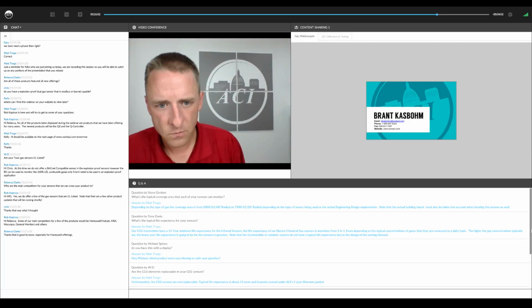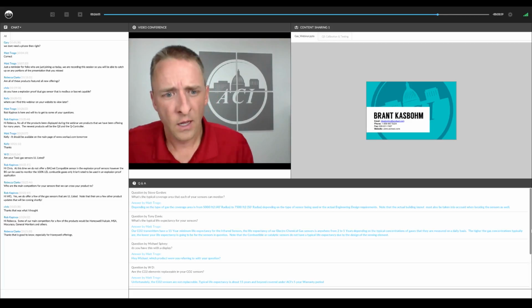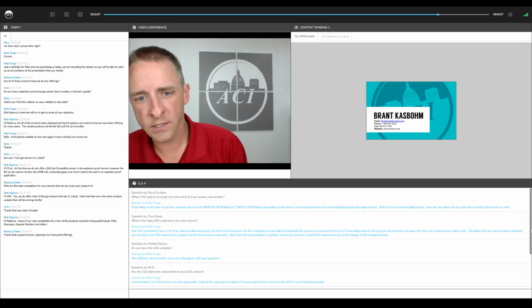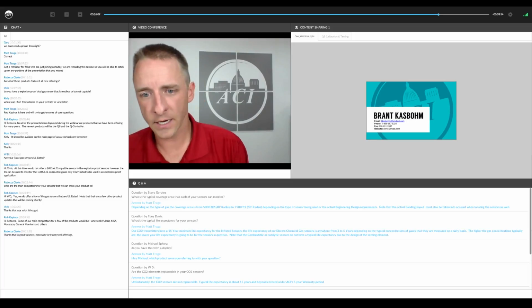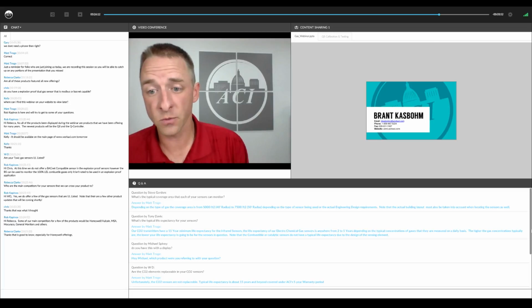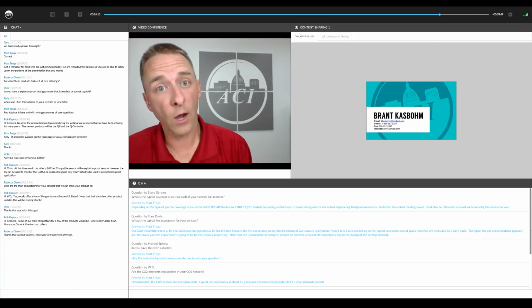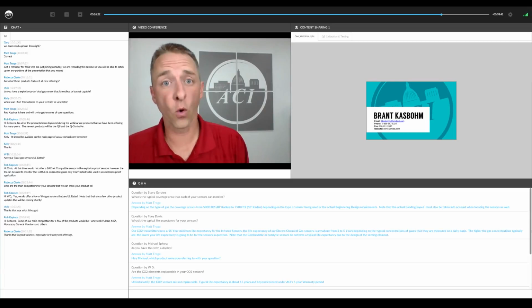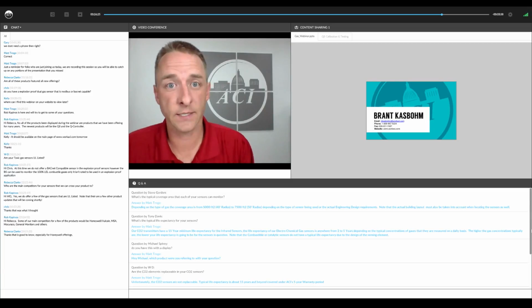A question: I have an existing LON talk system. Is there an option for LON gas detection, specifically CO, in addition to Modbus and BACnet? No, we don't have any type of LON output or a LON protocol for any of our gas sensors, and I don't know if that's available anywhere in the marketplace. Off the top of my head, I don't know of any LON-based or LON protocol gas sensors. So fortunately, it looks like LON is getting less and less common out there. So we just don't have an option for that.